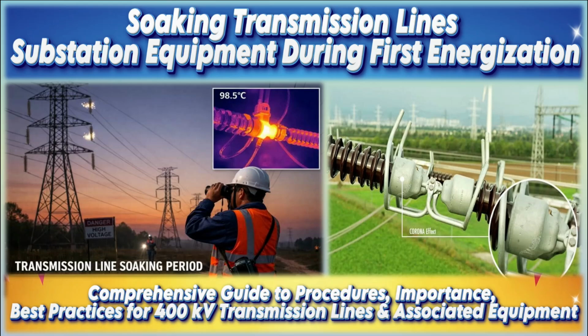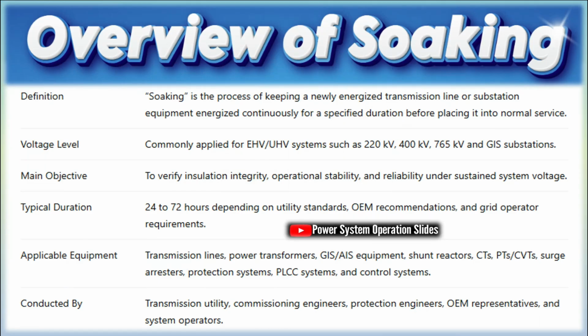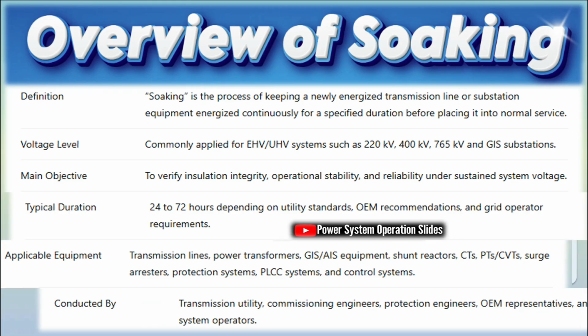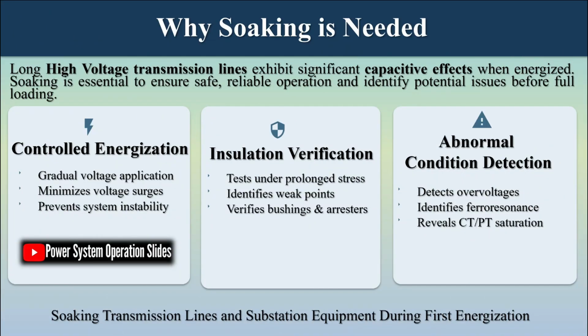The first energization of transmission lines, power transformers, and substation equipment is one of the most critical stages in the commissioning process of any electrical power system. Before newly installed or refurbished equipment is placed into full service, it must undergo a controlled energization period commonly known as soaking, voltage soaking, or pre-energization soaking.